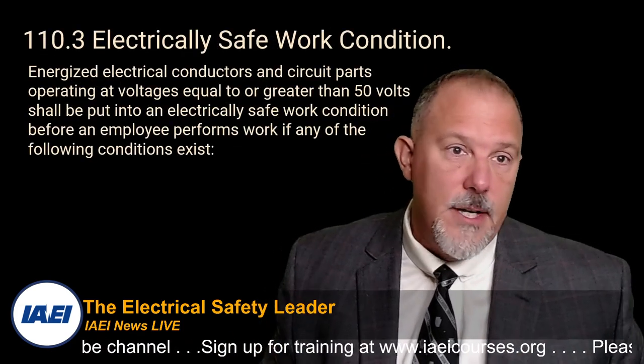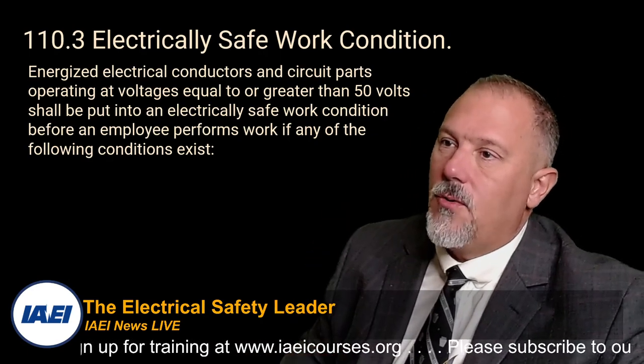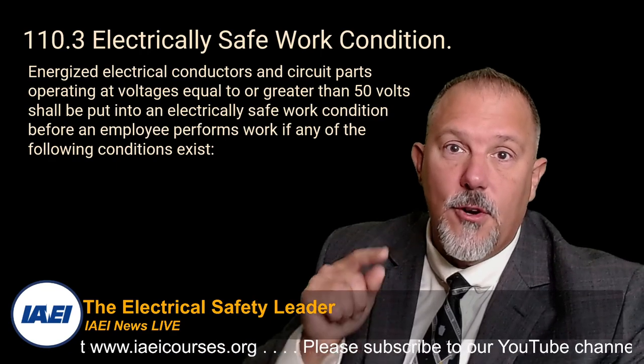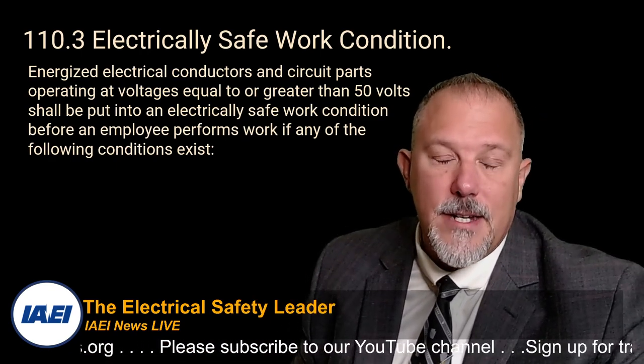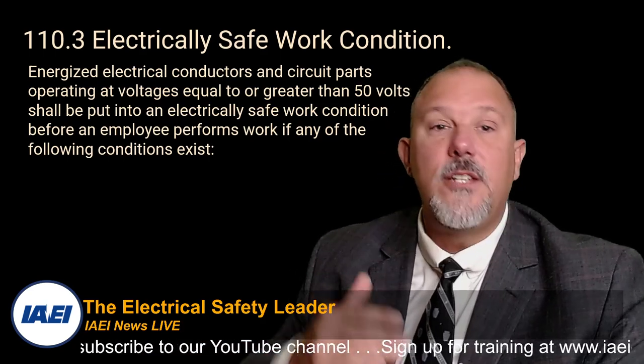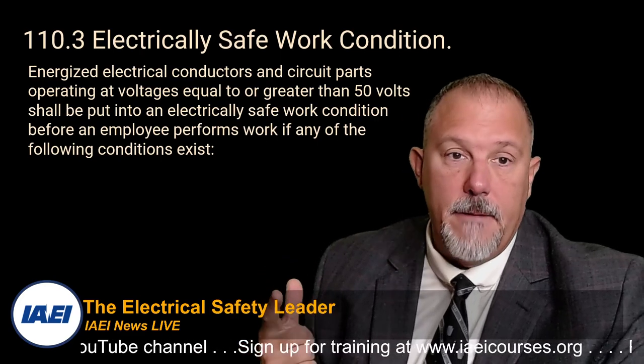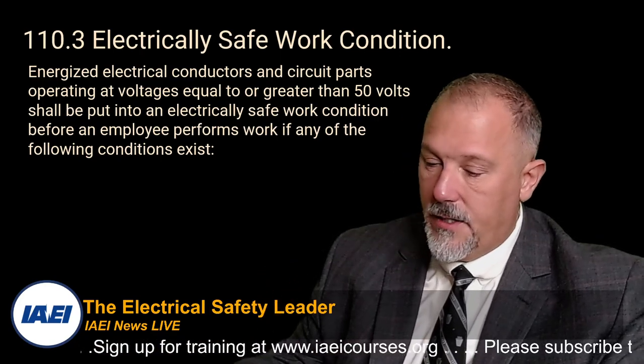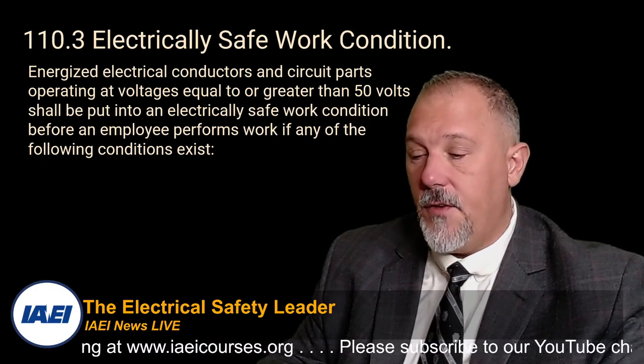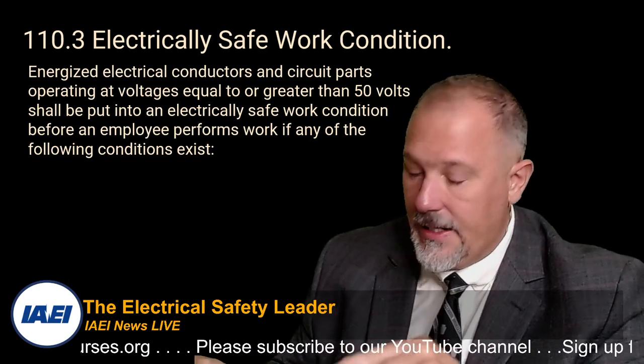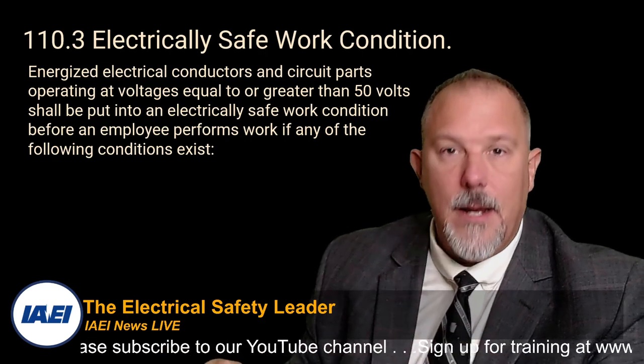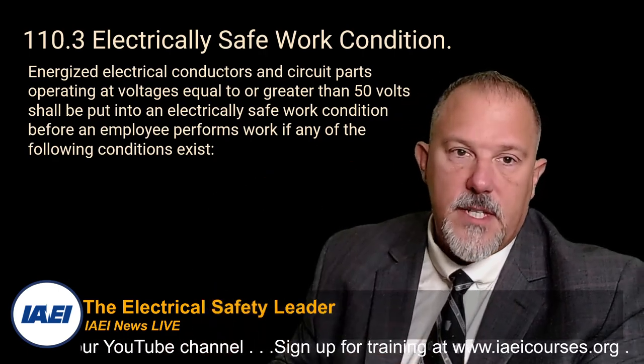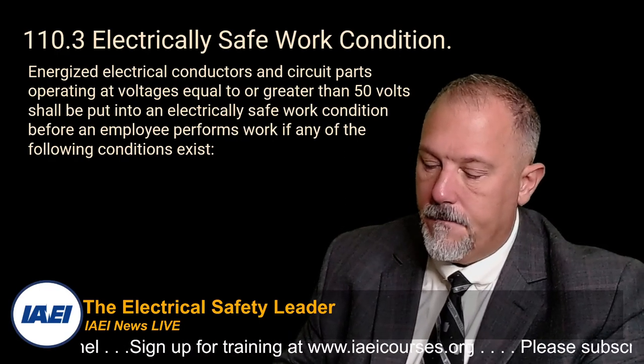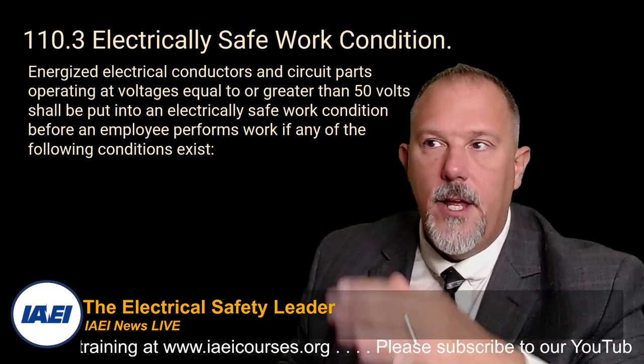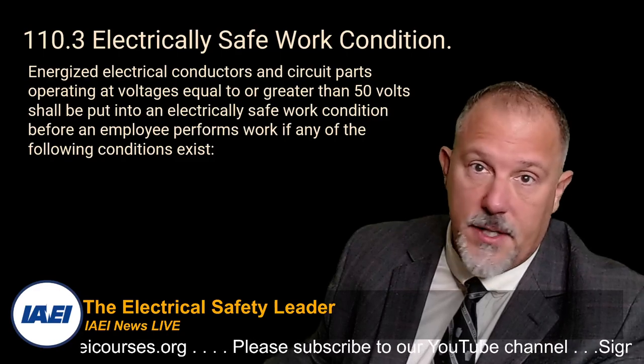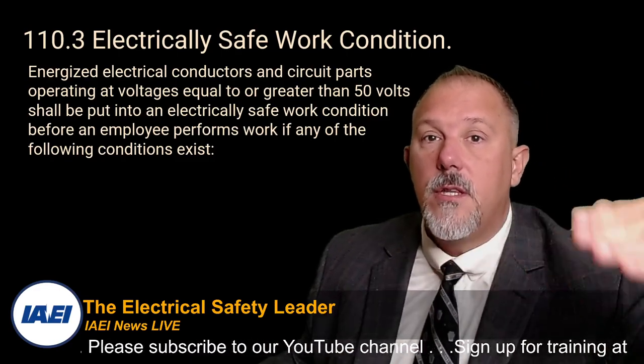Well, what 70E tells us in 110.3 is that energized electrical conductors and circuit parts operating at voltages equal to or greater than 50 volts shall be put into electrically safe work conditions. So if I'm less than 50 volts, I don't need to worry about a shock hazard, is what this is telling me. So let's take a look at 110.3. Now, just to give you an example, Article 110 in 70E is titled General Requirements for Electrical Safety-Related Work Practices. So it's important to understand the titles of the articles. Always work your way back up. If you want to understand a requirement, keep going up, especially if it's a first level or second level subdivision. You need to keep going further up into the code to say, what am I talking about?